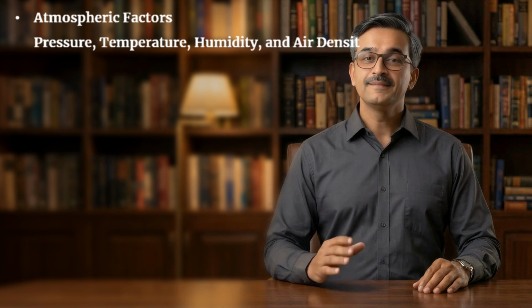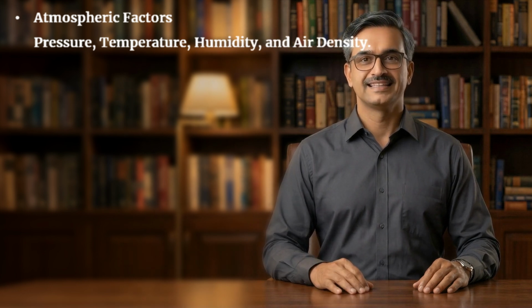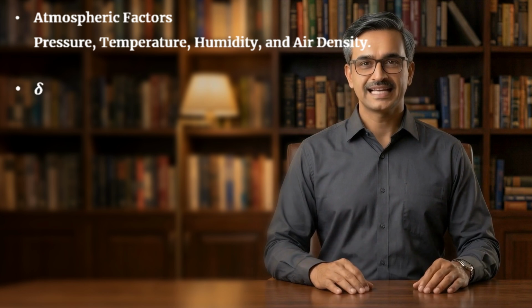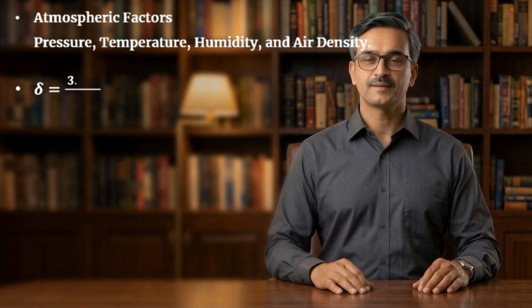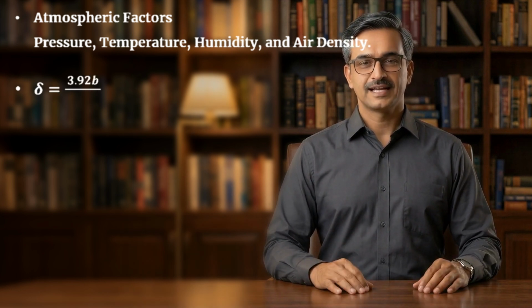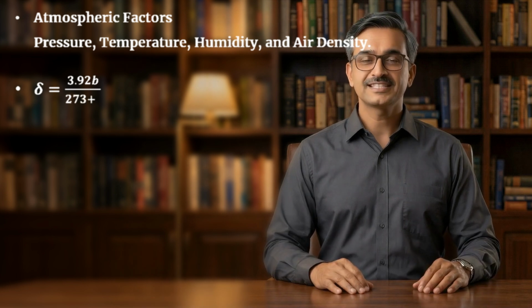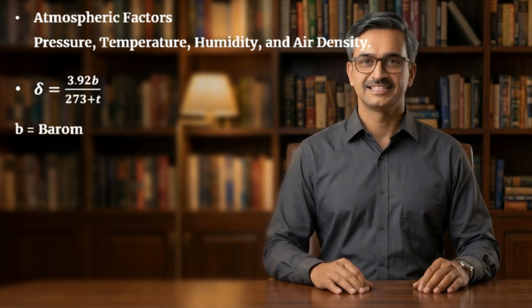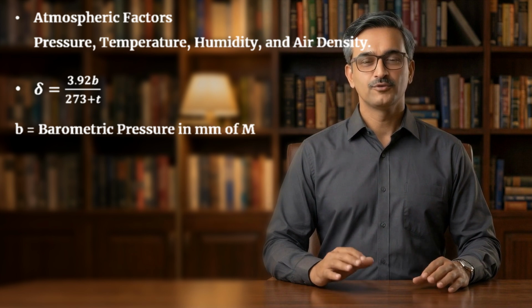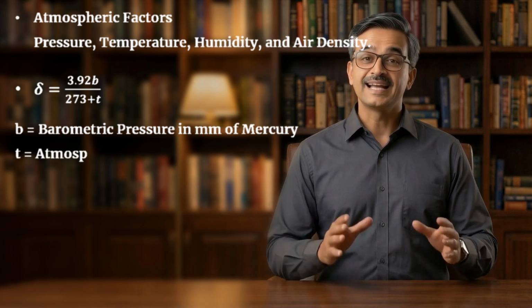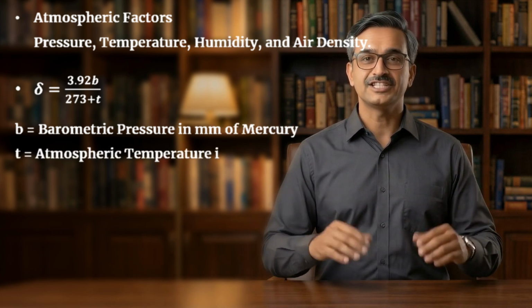Atmospheric conditions strongly affect corona because the dielectric strength of air changes with pressure, temperature, humidity, and air density. The air density factor is expressed as delta equals 3.92 multiplied by b divided by (273 plus t), where b is barometric pressure in millimeter of mercury and t is atmospheric temperature in degrees Celsius.